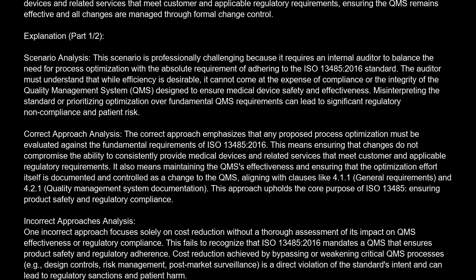Correct approach analysis. The correct approach emphasizes that any proposed process optimization must be evaluated against the fundamental requirements of ISO 13485-2016. This means ensuring that changes do not compromise the ability to consistently provide medical devices and related services that meet customer and applicable regulatory requirements. It also means maintaining the QMS's effectiveness and ensuring that the optimization effort itself is documented and controlled as a change to the QMS, aligning with clauses like 4.1 General Requirements and 4.2 Quality Management System Documentation.